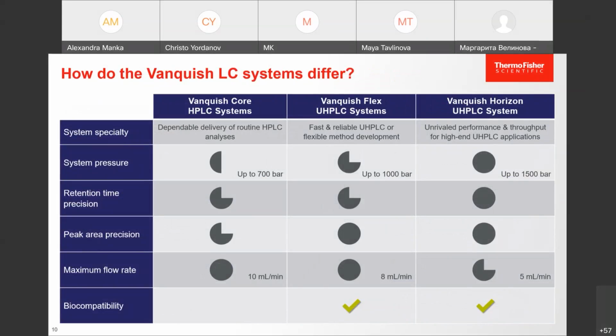When we compare now, again, the Vanquish Core with the Flex and the Horizon, so these are our three tiers. The Core is really our routine HPLC system. It can go up to 700 bar, while the Flex is more our UHPLC and HPLC system for flexible method development, and it can go up to 1,000 bar. And then we have the Horizon that goes up to 1,500 bar with unrivaled performance and throughput for high-end UHPLC applications.